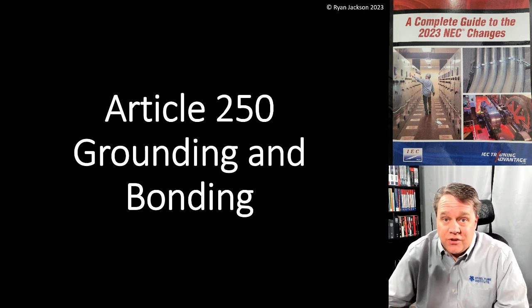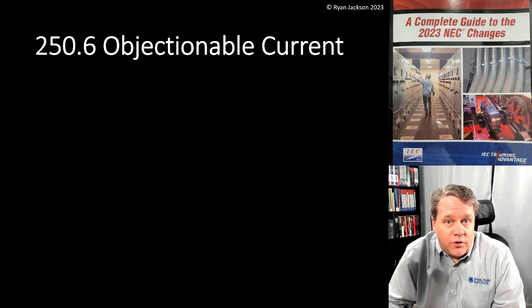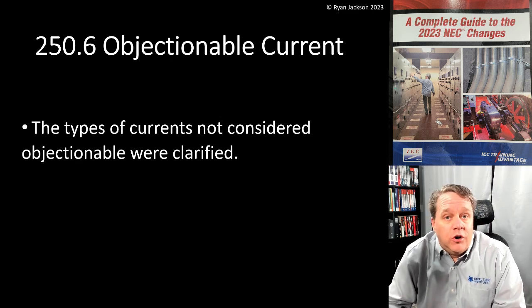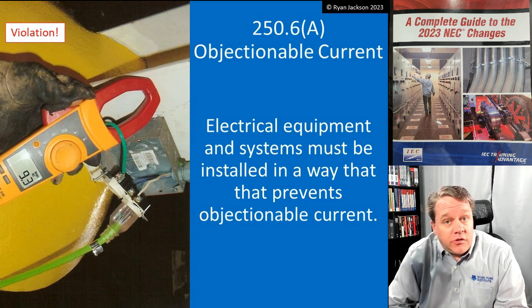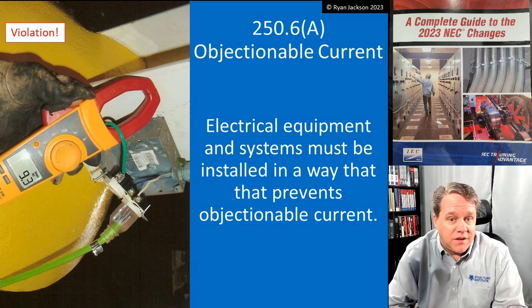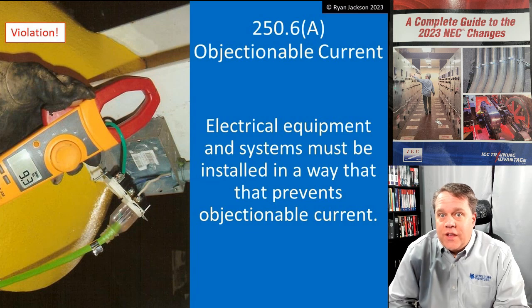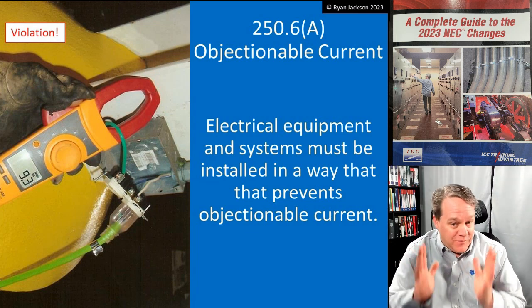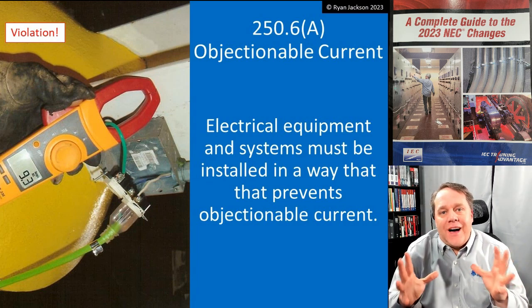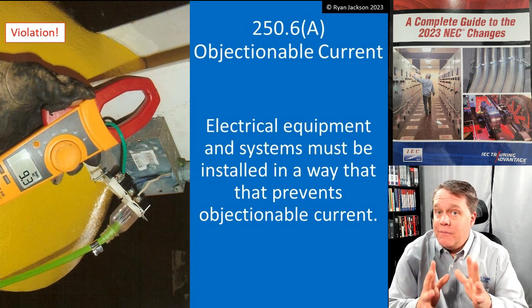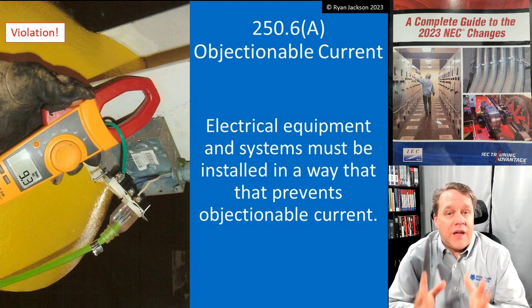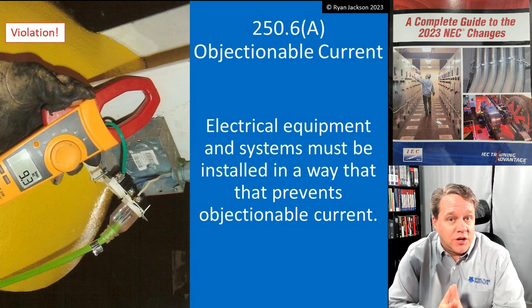Let's start with 250.6 objectionable current — I like what they did here. The types of currents that are not considered objectionable were clarified. Every three years like clockwork somebody wants to define the term 'objectionable current,' and I get that, because the code says you can't have objectionable current but doesn't tell you what that is. Electrical equipment and systems must be installed to prevent objectionable current. Objectionable current is basically neutral current flowing on green wires and metal objects.